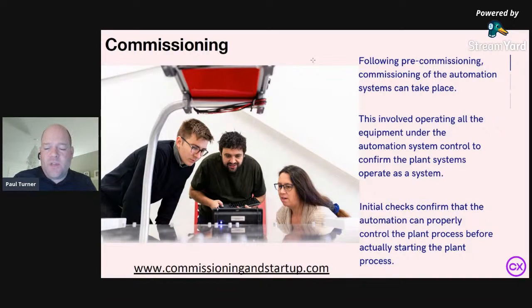Now, because this is without the plant fluids in there, your tank is likely dry and has no liquid in it. So through some of this, you may be stimulating the level sensor. It could be various different methods, even something as simple as a piece of cardboard on the end of a stick to confirm that you're triggering the level sensors, to then see the high level trigger and watch the process logic function correctly to turn on a single pump, turn on the next pump, and ensure that your system reacts accordingly. Through this testing of the logic functions, you're going to want to test all of the normal operating conditions, but you're likely going to want to test all the fault scenarios as well.